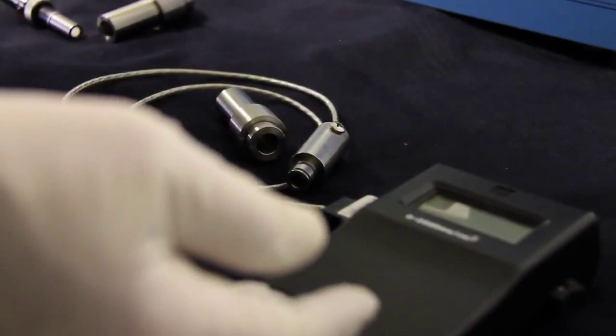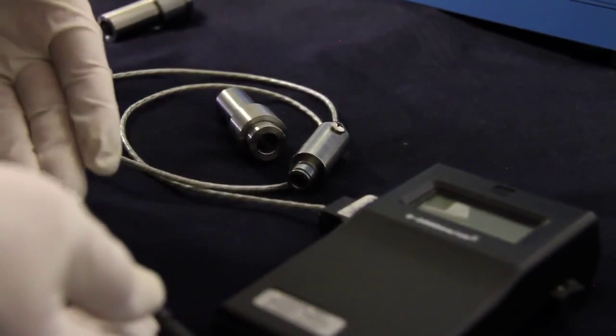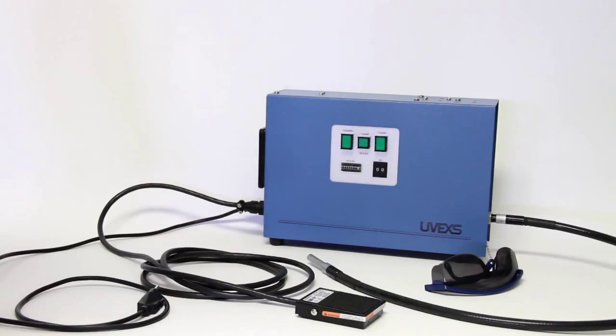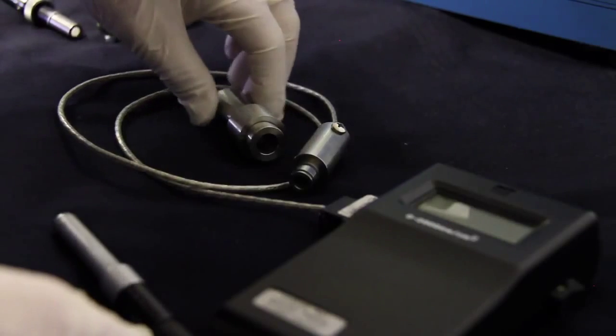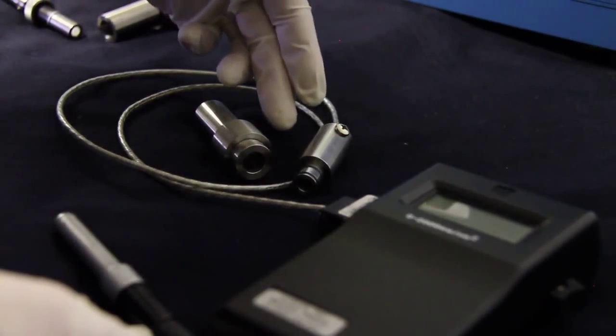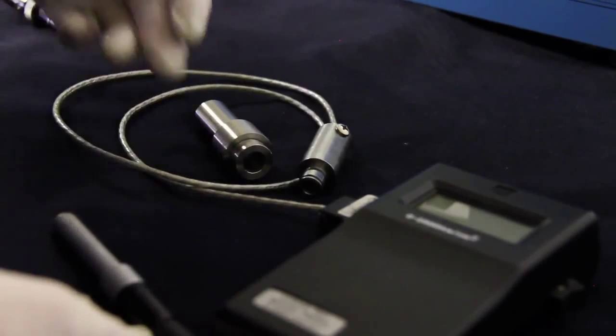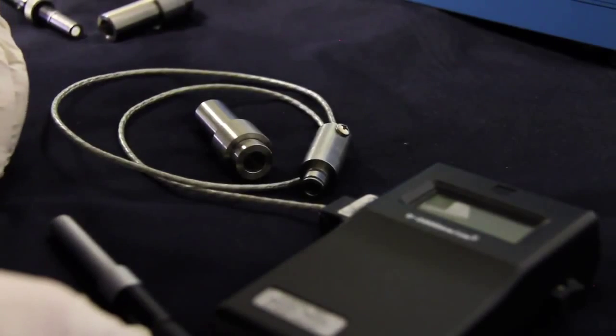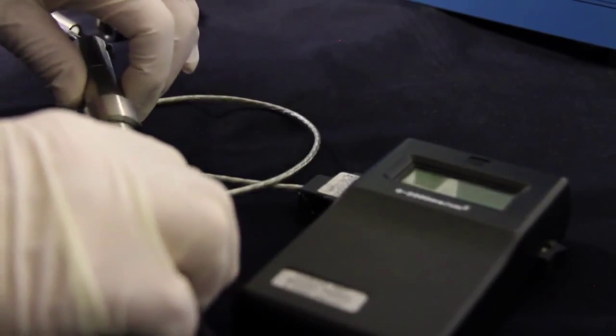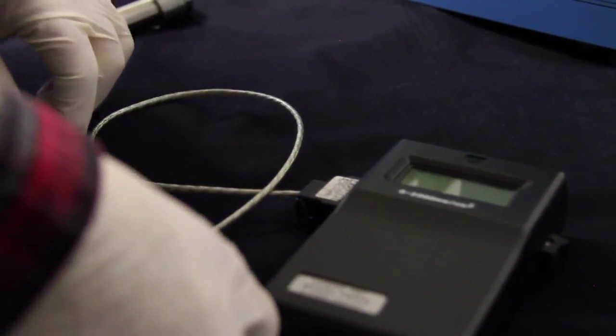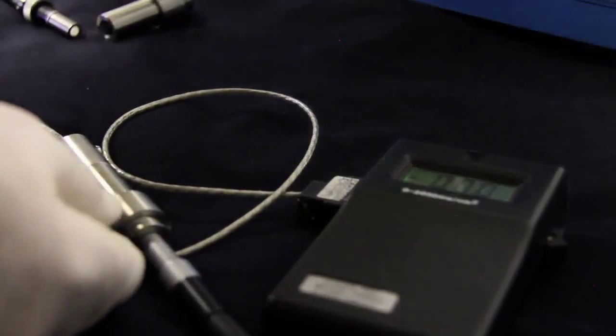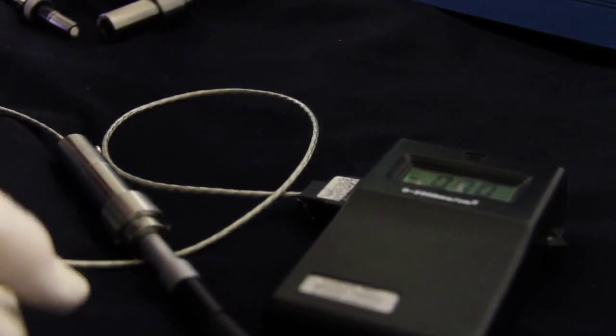If you want to use the PM600 system to measure UV intensity from the SCU-110 spot cure, a variety of adapters are available with the probe for that, so you can attach it either to the wand end or to the end of the SCU-110. With the adapters attached, you can then put the wand into the adapter, and when you put the UV on, it'll measure the UV intensity at the end of the wand.